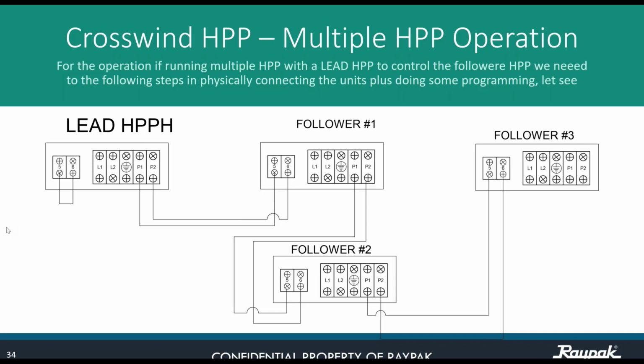Can we make a connection? There was somebody in the other class asking, can we make a connection to override the timer in order to start the heat pump? Yes, we can do that. I apologize that I cannot show you the diagram right here, but it's going to be explained in tomorrow's class on troubleshooting. But we can do that also. The connection has to be through P1, P2 going to a relay, and from the relay we go to the pump. Yes, we can also do that.